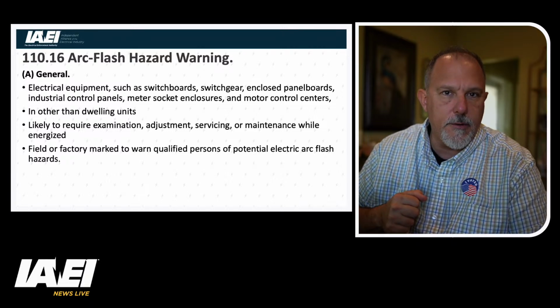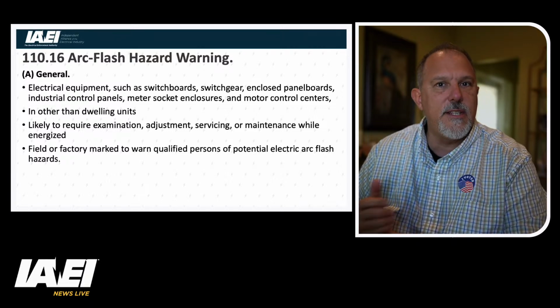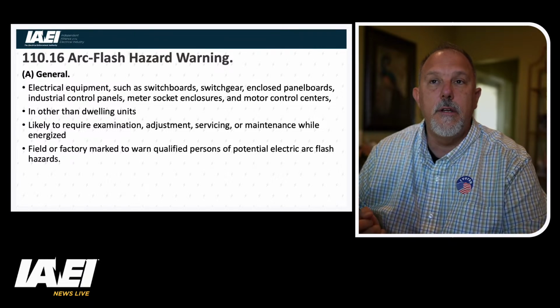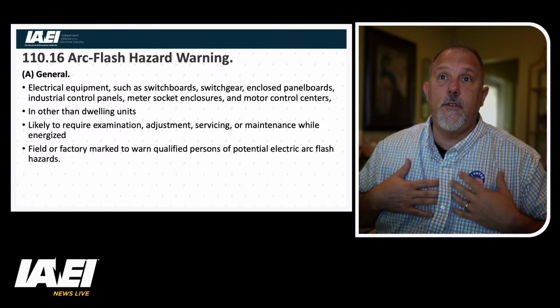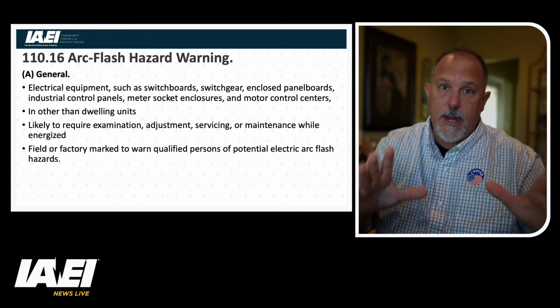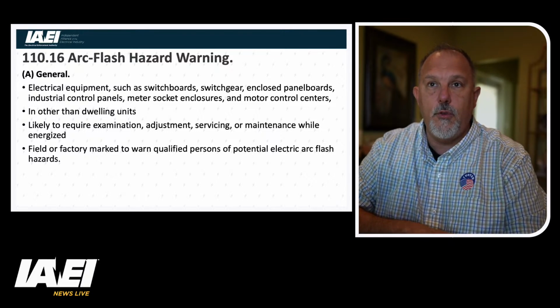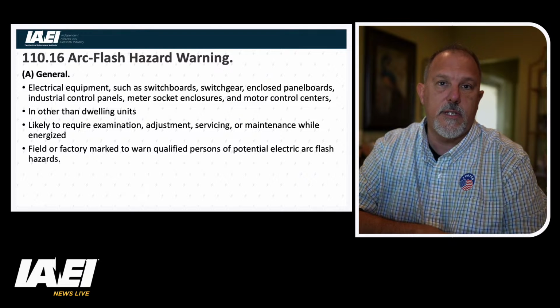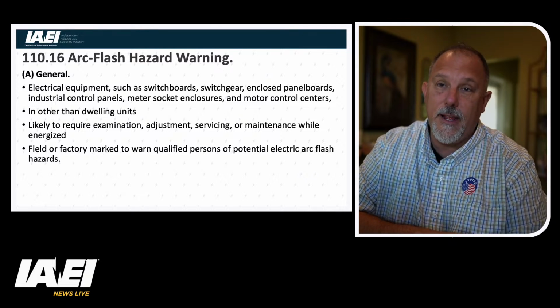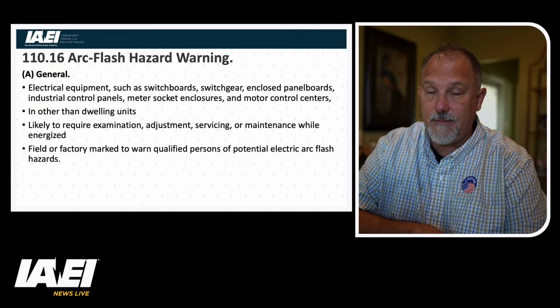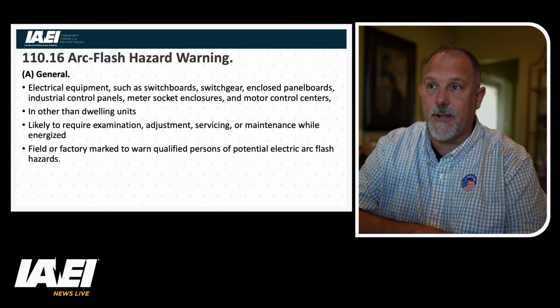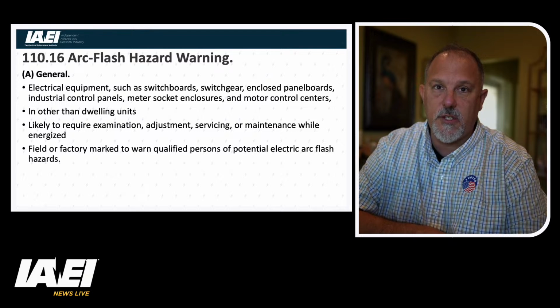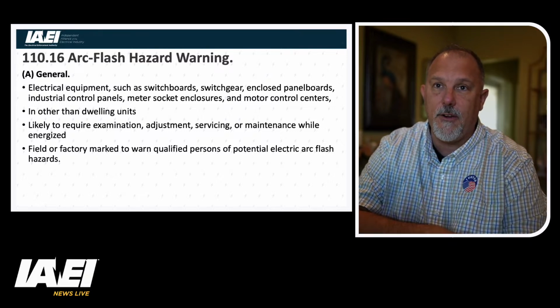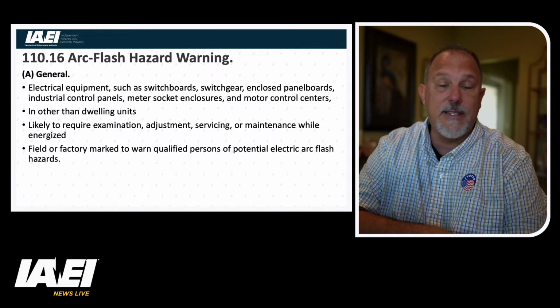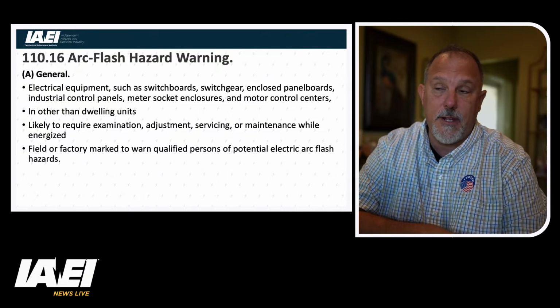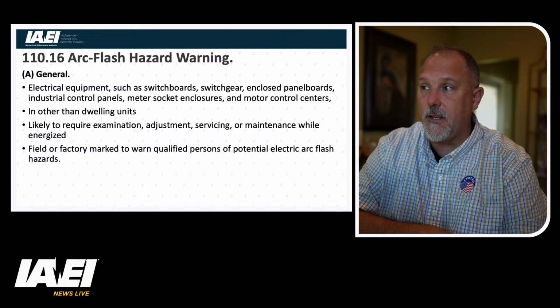Panel boards are no-brainers. That non-fused disconnect, that transformer. I would almost argue if you want to remove all doubt, put an IR window on there. You could have an inspector or someone say, well, how are you going to do the infrared? It has to be done while energized. And you're going to have to open that door. You're going to have to expose the energized parts to prepare for the IR scanning. I could see that debate going on. I don't know if it's ever occurred. I can definitely see that debate occurring.